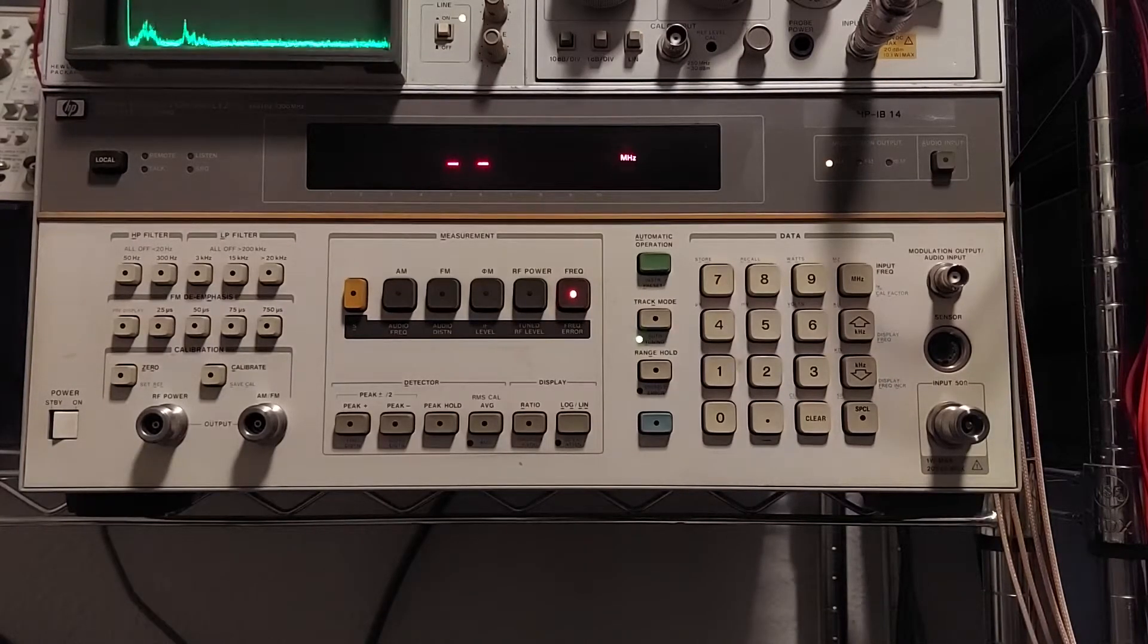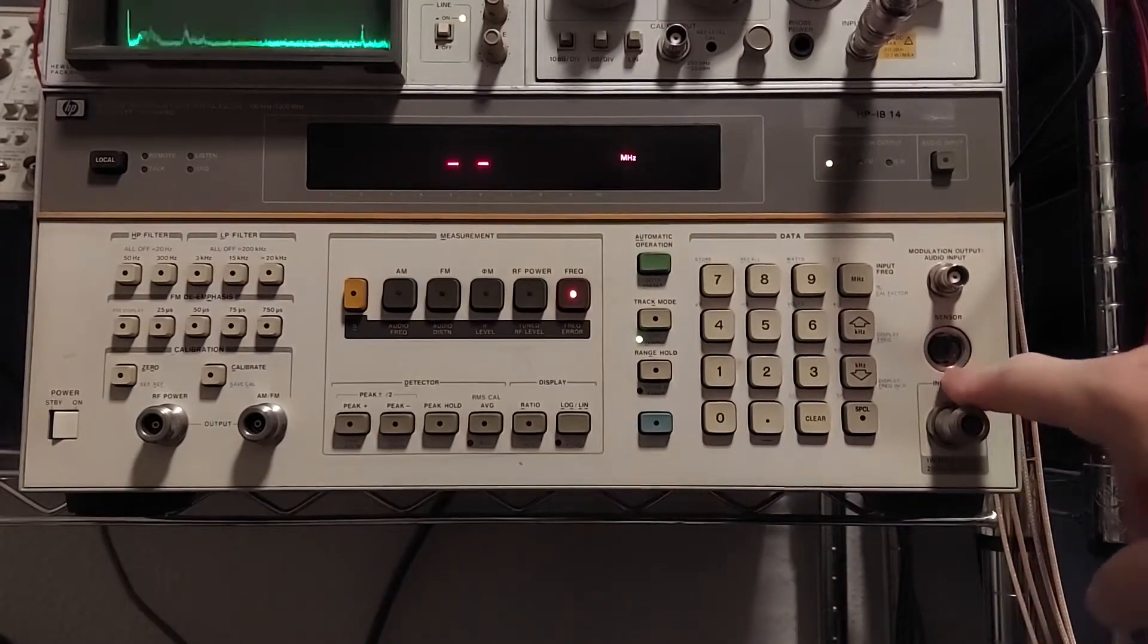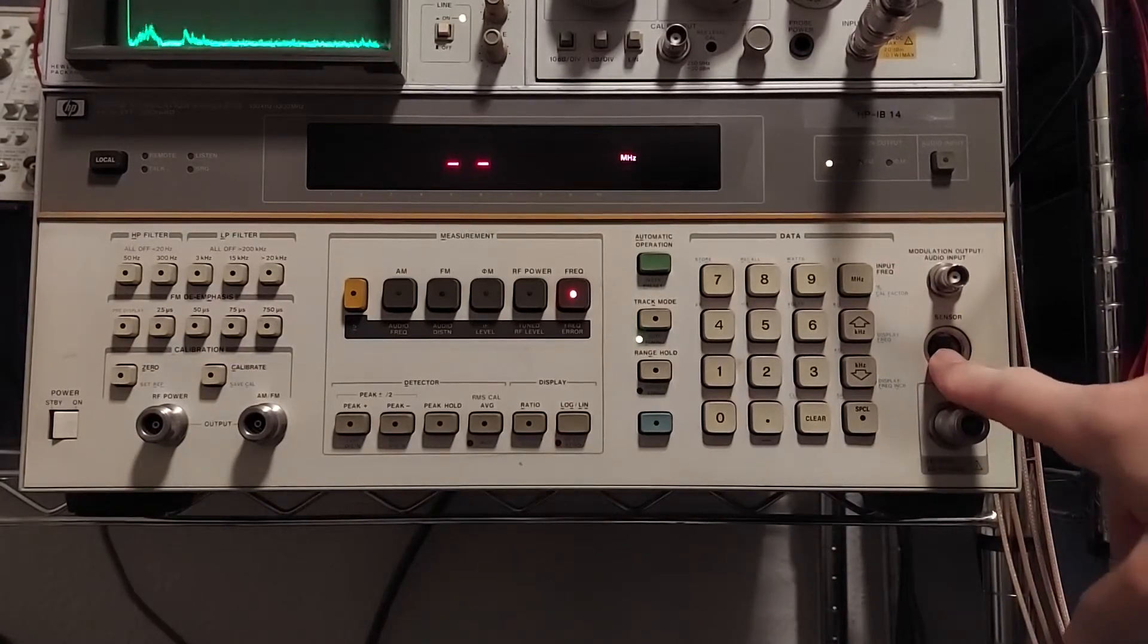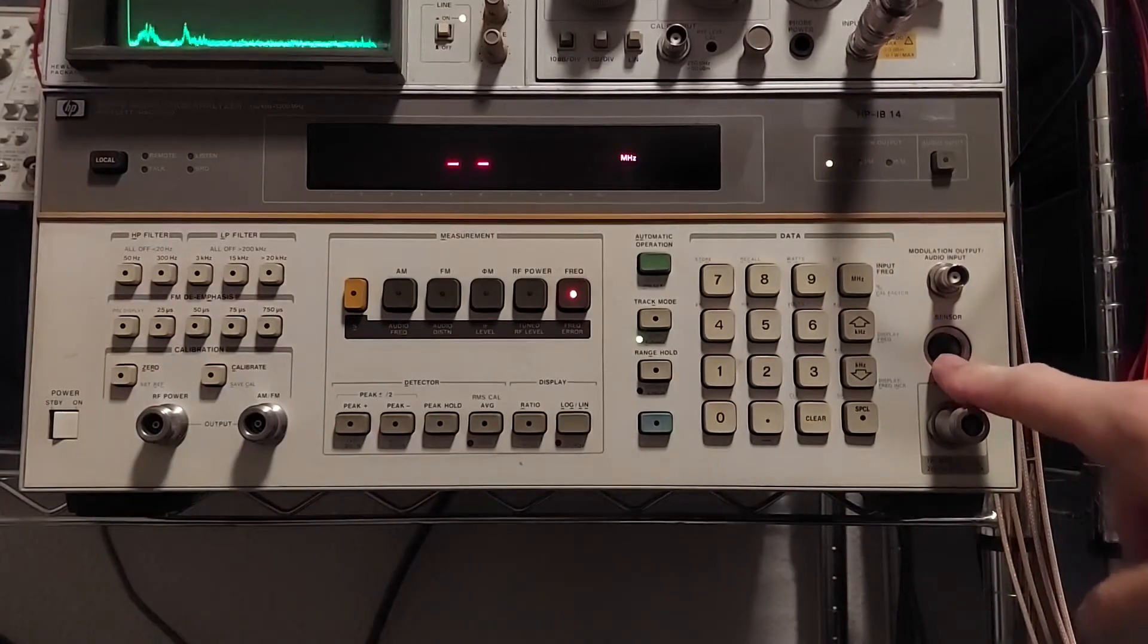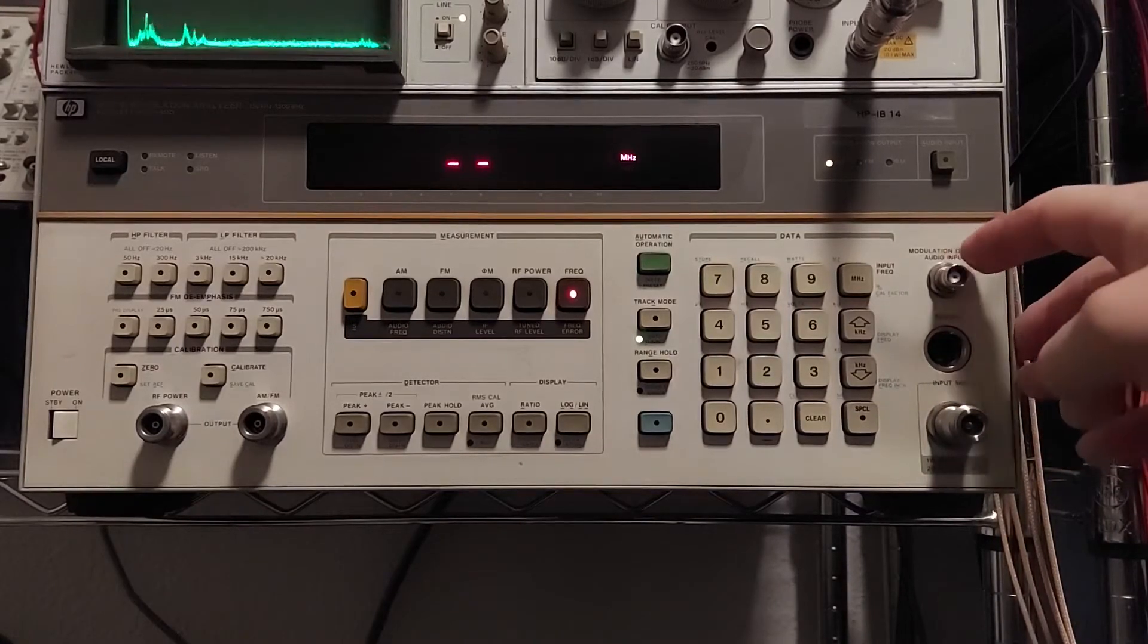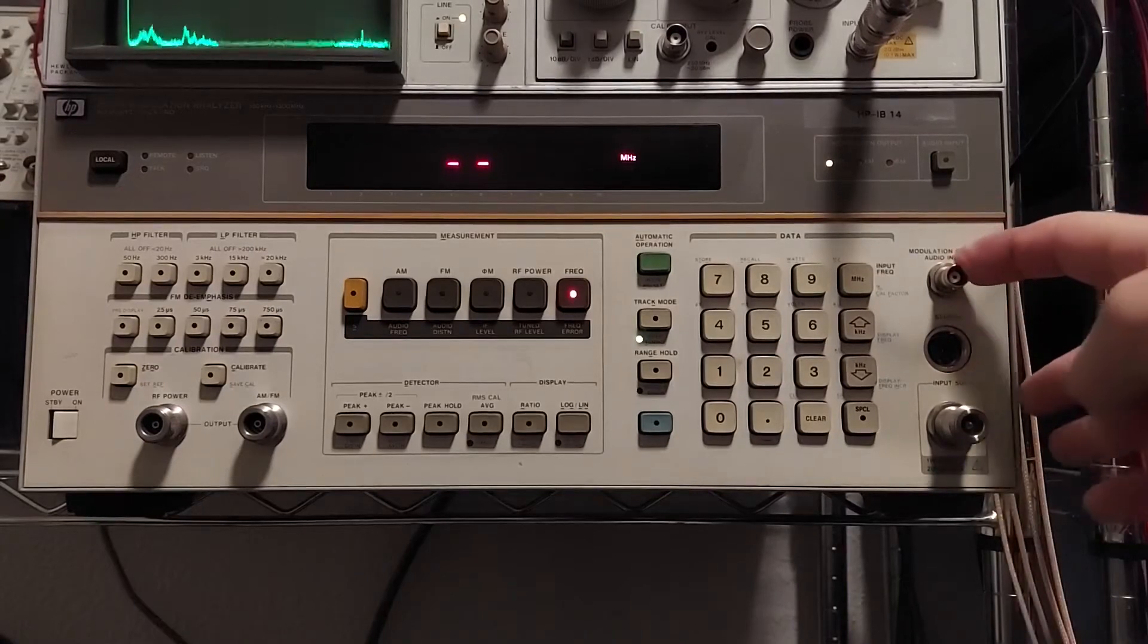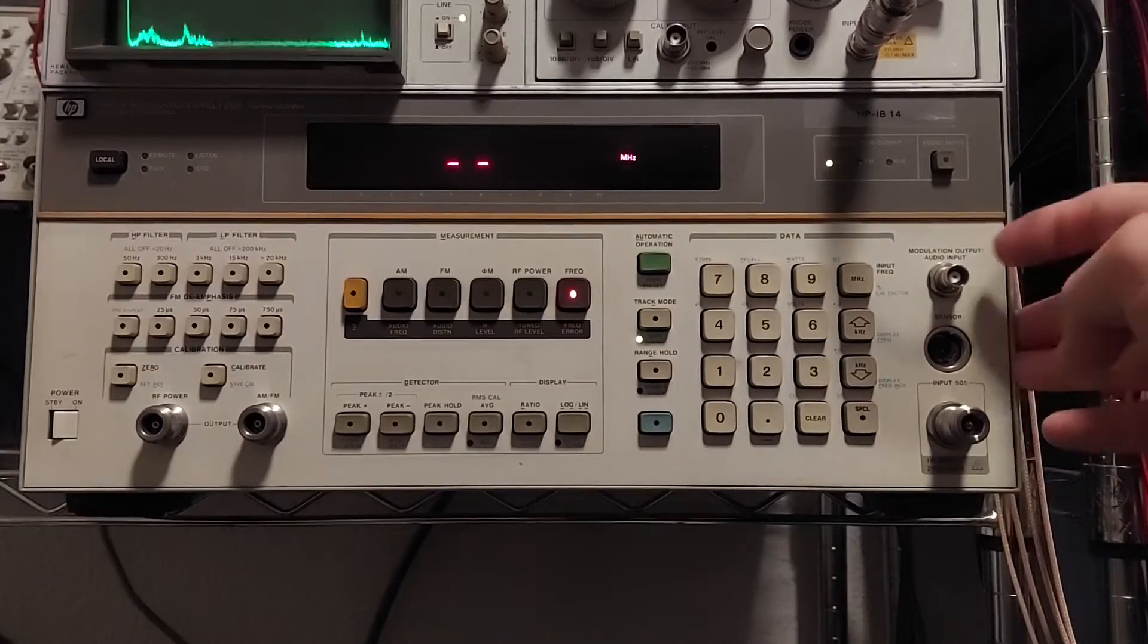But essentially this thing is also a power meter. It will accept the HP power sensors for like the 437B power meter. You can also insert audio and do SINAD measurements, which is kind of nice. Here lately I've just been doing all those manually. And now I've got an instrument that I can actually make them direct.